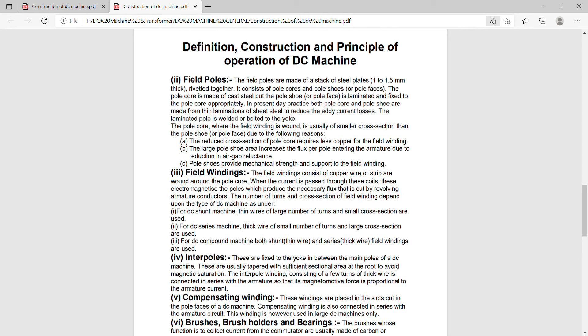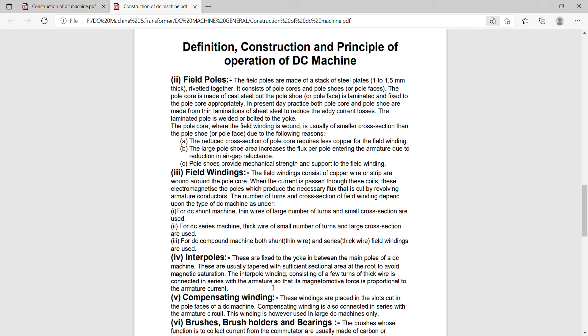Interpoles. These are fixed to the yoke in between the main poles of a DC machine and these are usually tapered with sufficient sectional area at the root to avoid magnetic saturation. Its function is to compensate the armature reaction, to neutralize the armature reaction.